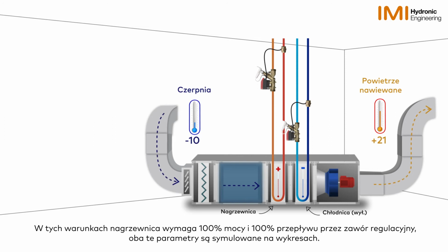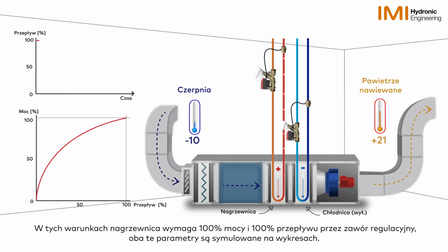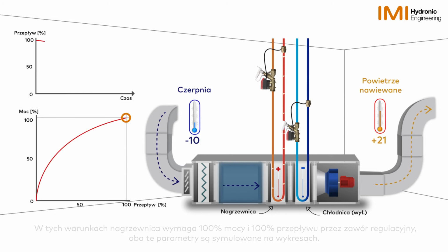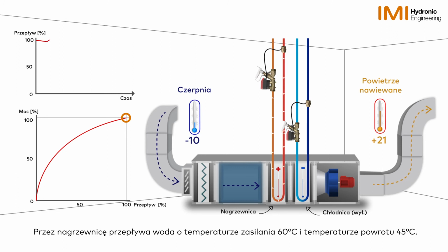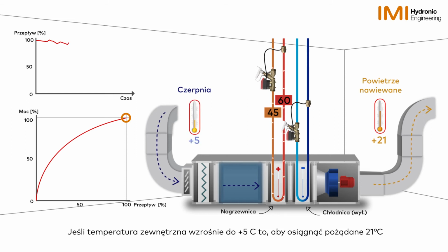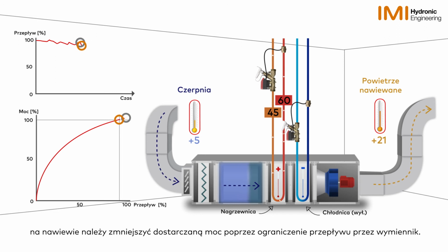In this condition, the heating coil requires 100% power and 100% flow from the control valve, both simulated in the graphs. Water is passing through the coil with a supply temperature of 60 degrees and a return temperature of 45 degrees C. If external temperature increases to 5 degrees C, to achieve the desired 21 degrees C, the power supplied needs to be reduced by limiting the flow through the unit.